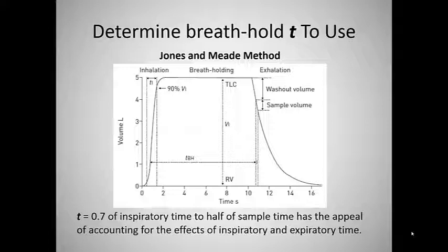Do we do it at the beginning of inspiration? Do we do it at the end, when we get to full capacity? When we start blowing out, there's a couple of seconds emptying your dead space. At what point does that become important? So we're consistent in doing that. We start our time measurement, our clock ticking, at 7/10 into the inspiratory phase to reach full capacity.